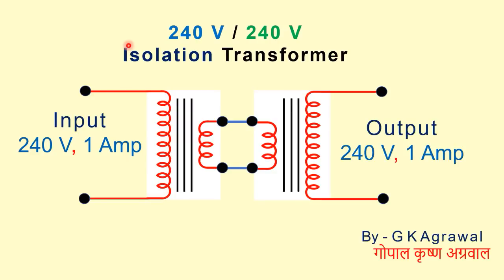Now, this has become isolation transformer 240 volt by 240 volt. I have used two transformers, one here, one here. They are connected back to back. If we give here 240 volt, here we will get 240 volt. There will be double isolation, one here, one here. Percentage impedance of this transformer will be double than the normal transformer.